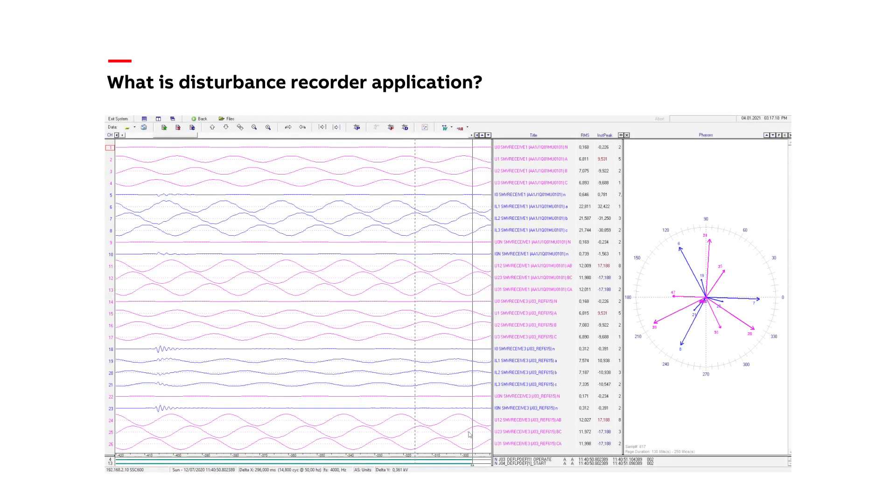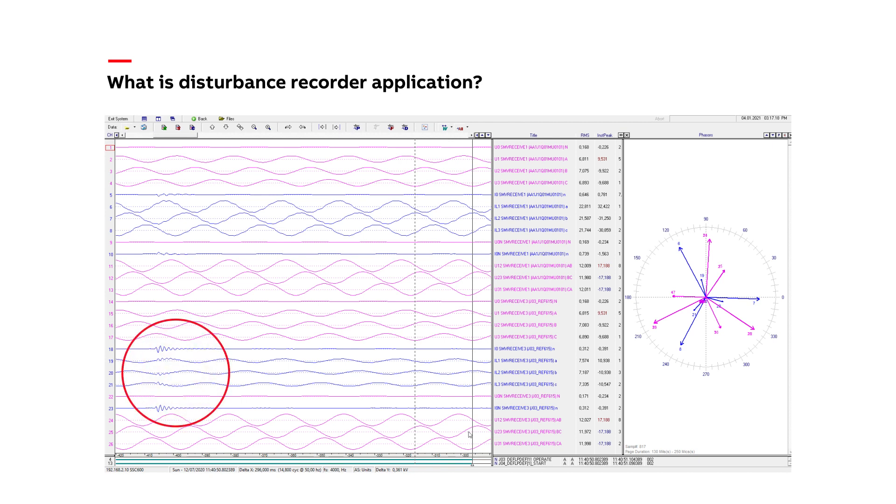Most importantly, we can also see what happened. For instance, this is a screenshot from WaveWin, a software tool for analyzing disturbance recordings. Here we can see that there was some kind of disturbance in the system. We can read the values and see in which phase of the three-phase system there was the most disturbance, and we can also see other data.